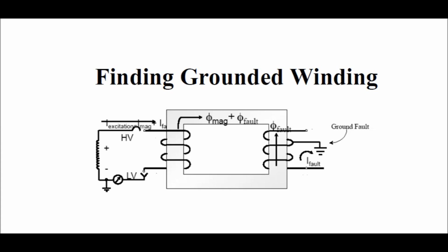Besides finding the interturn fault, it also helps in finding a grounded fault in either side of the winding. Here the secondary side of the winding is grounded, and due to this a current will flow from the secondary side winding to the grounded path, as shown in this diagram. Due to the flow of current to the grounded path, that is I fault, a flux will flow in the core, and it will oppose the magnetizing flux phi mag. Due to this, the primary winding will draw more current to nullify the effect of the flux phi fault. Therefore, during this test, the excitation current will be much more than the normal condition. Similarly, it will help to detect any fault in the load tap changer winding in a similar way.